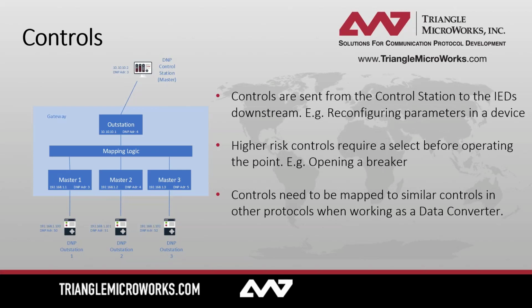This is just an extra security step that we put in between the operate. It essentially allows the device to know, I'm going to be performing this higher risk control, and then you have a certain time to actually issue that control. That way someone doesn't misclick something or send the wrong control by accident from the control station. Controls do need to be mapped to similar controls in other protocols when working as a data converter.